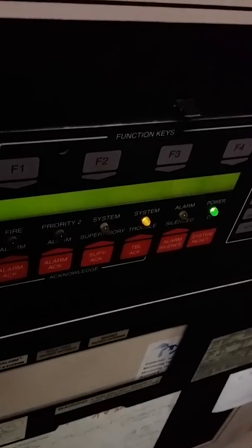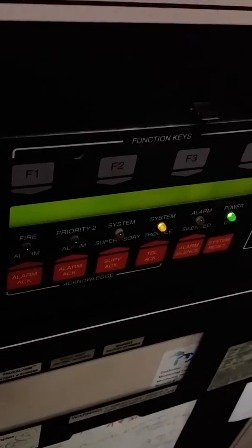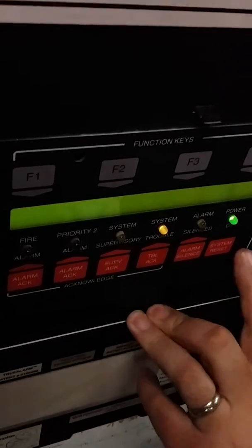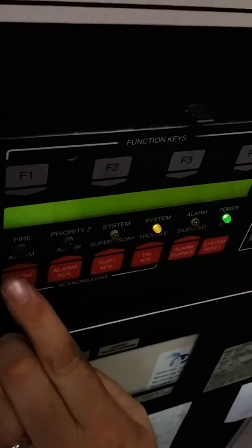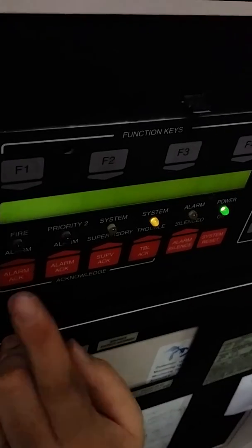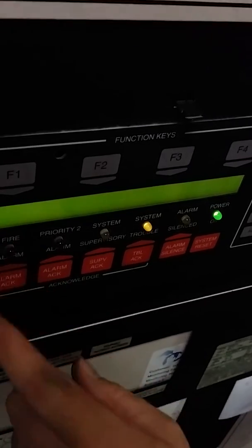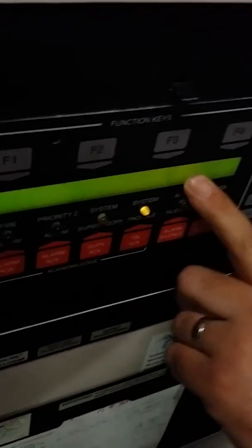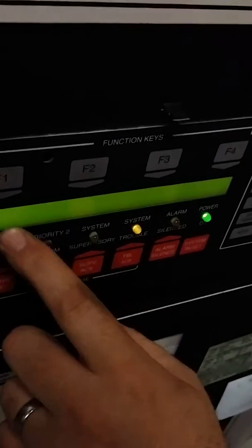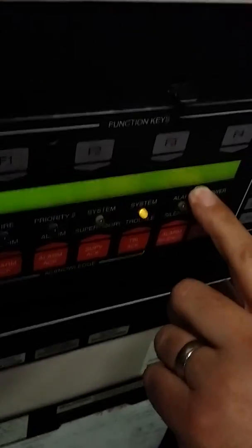That is correct. Under normal circumstances, you can't just reset unless you're clear to do so. So that's where you're careful. Now, the system will not reset if there's an active alarm. So what you can do, if this were coming up as an alarm over here, you'd cycle through and you'd see it. It would say 4th floor, and down here, it would say normal or alarm. If it says alarm, you're not resetting the system.